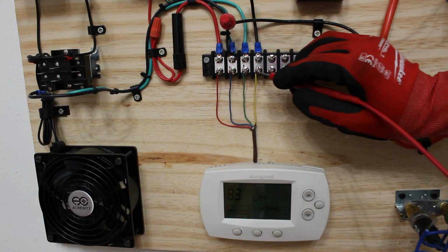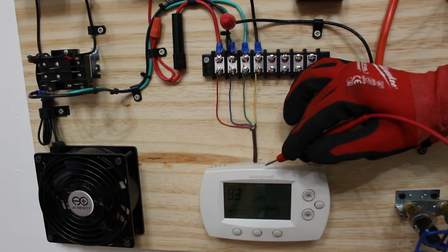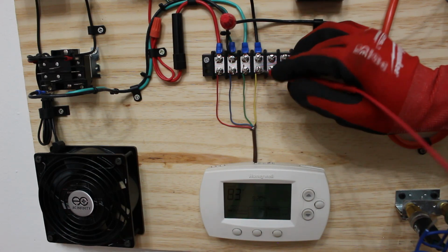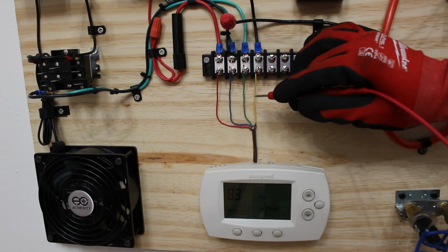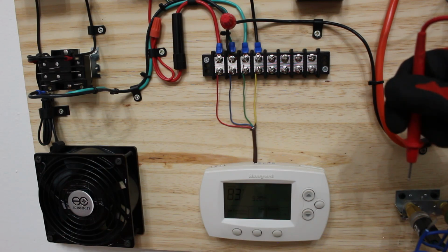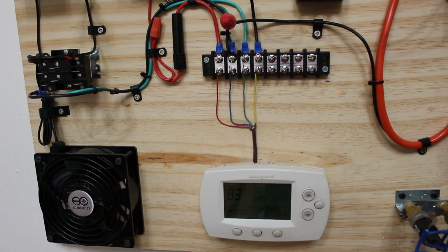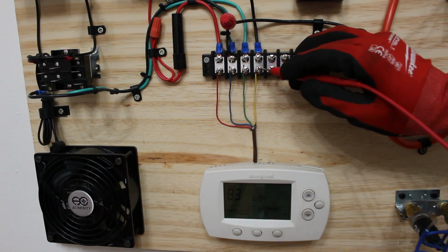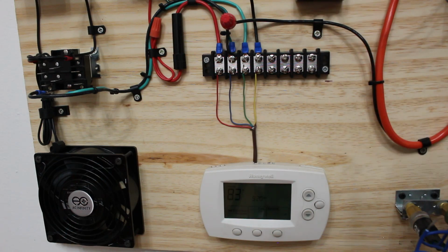So what we're gonna wanna do is take this yellow wire coming out of our thermostat, disconnect it from this low voltage terminal block, and from there, we're gonna go into the low pressure control, and then out of the low pressure control into our high pressure control, and then out of our high pressure control, we're gonna put it back into the circuit so then it can continue with its operation.